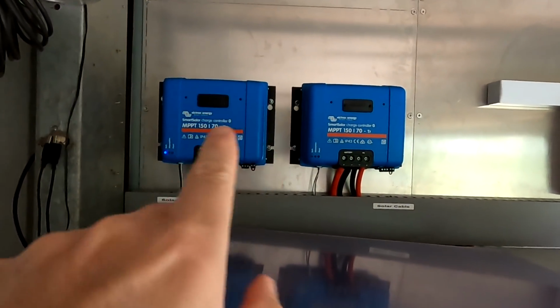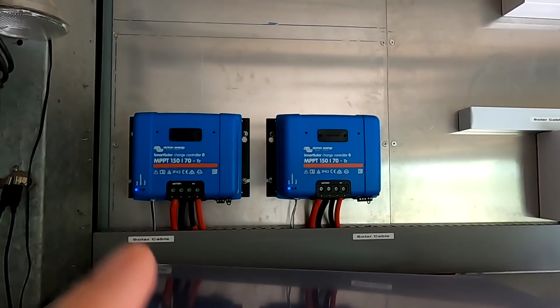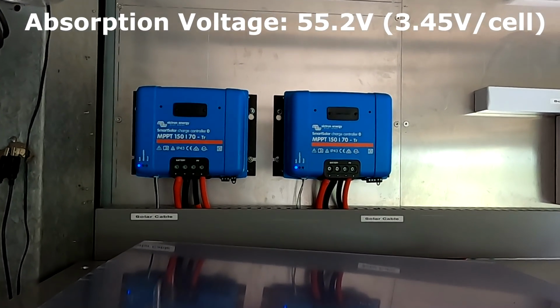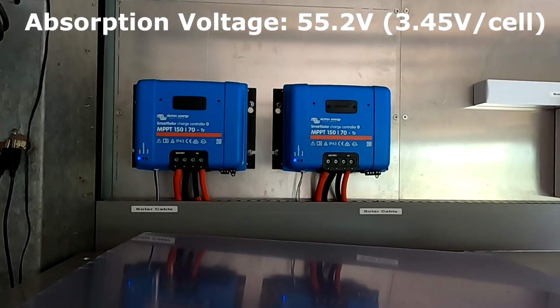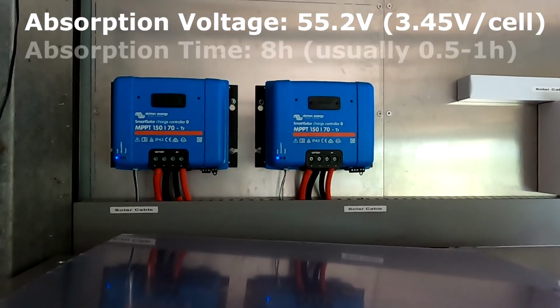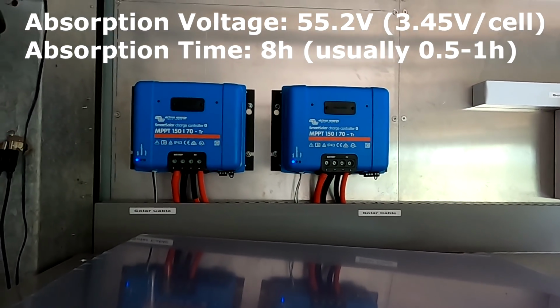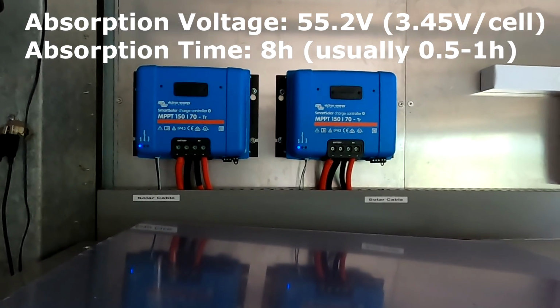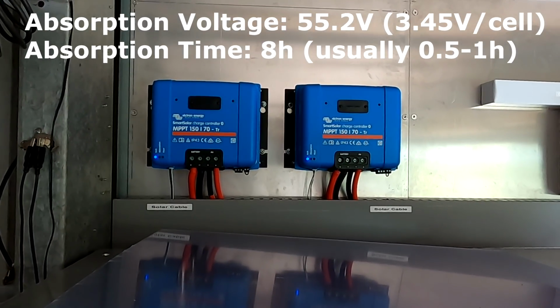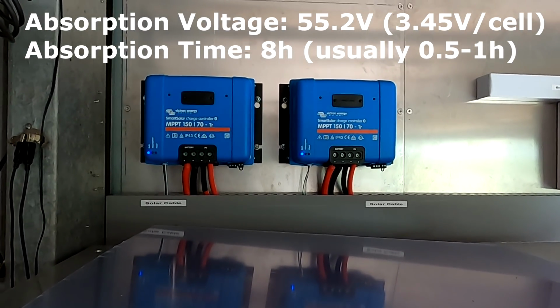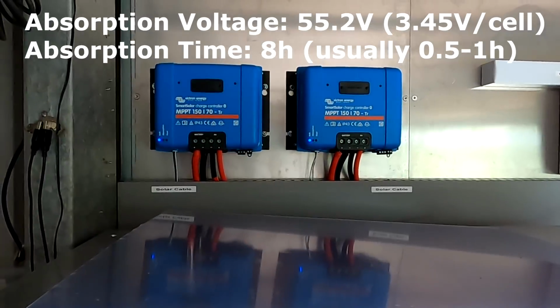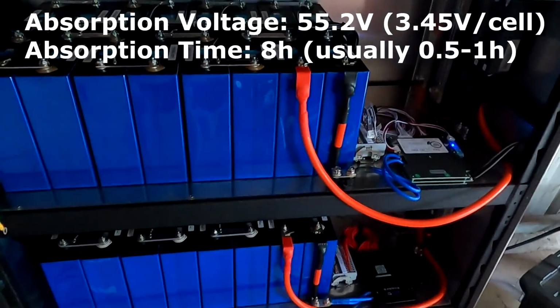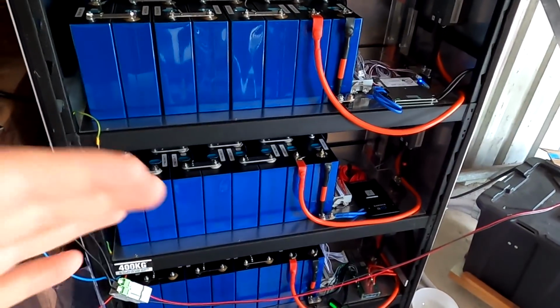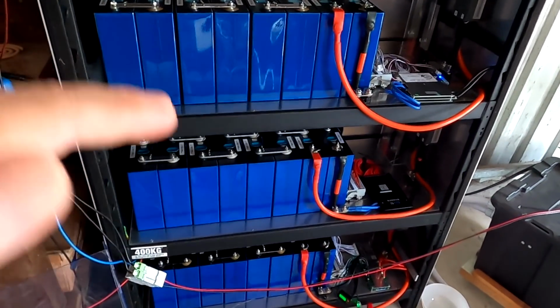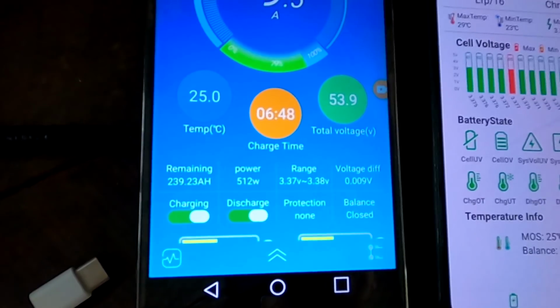So all 3 solar charge controllers are sitting on 55.2 volts, which is my absorption voltage. I have set the absorption time to 8 hours. We are not going to keep the battery on 55.2 for 8 hours, but this is more for the testing we are doing now. I want to keep the 55.2 for an extended period of time now to do some measurement and to see how the balancing works and to see how the overall performance of these 3 batteries is at this voltage.